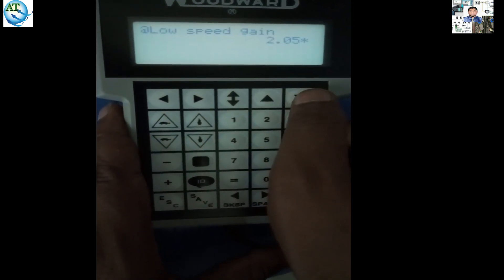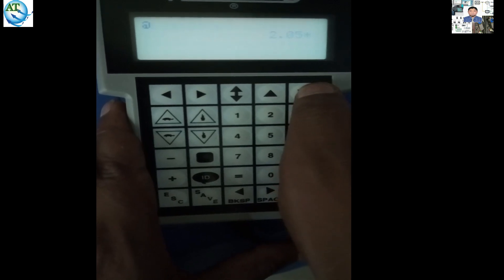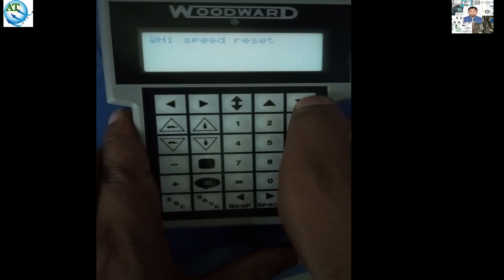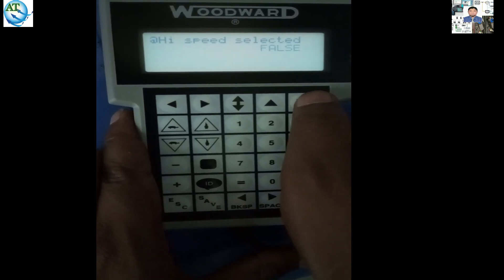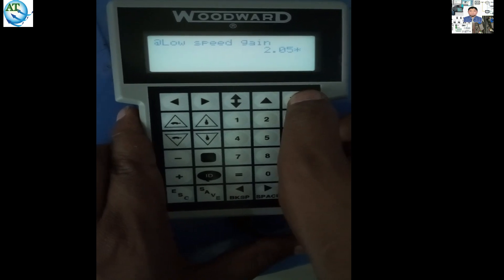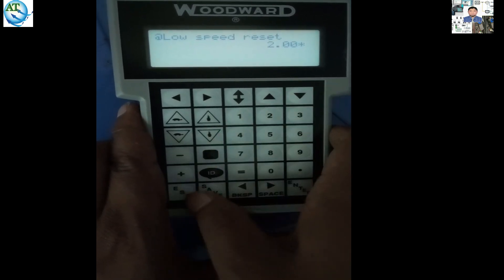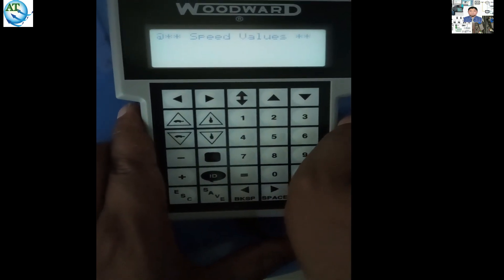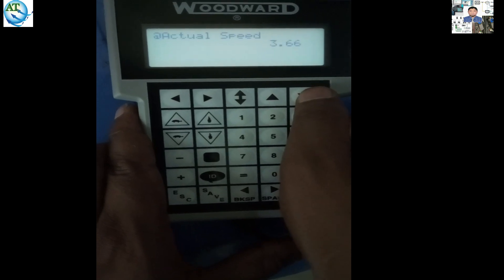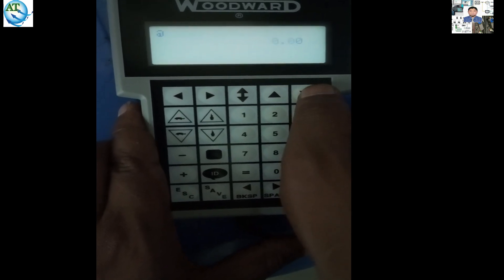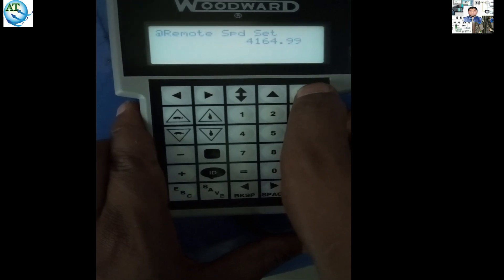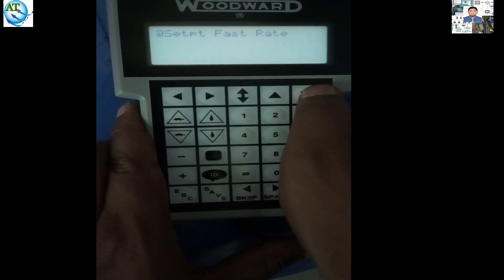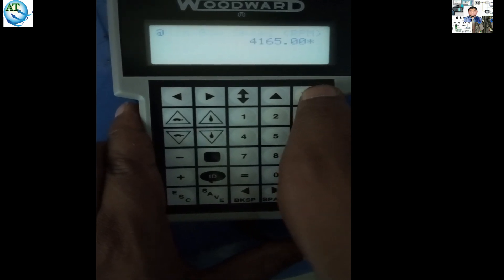Press the down key and go to the different options already configured here, such as speed dynamics. You can get another option. If you want to change any one, you can press the enter button and go to edit mode. I am not showing the changing option here — I am just showing how to use the handheld programmer and how to take backup, step by step. In the previous video I described the different function keys of the handheld programmer; the link is available in the video description.